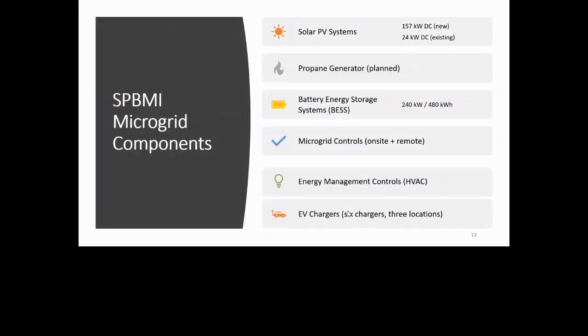So what did we install at our microgrid? These were all of our components. Solar PV, we installed 150 kW of new solar, which was through canopy parking. We had an employee parking lot that we did canopy parking with solar. We had existing solar at our education center, and we actually just put in a propane generator as an additional backup system. We have our battery energy storage system, which is all the batteries in a large box like a Connex box, and the controls are on site and remote.